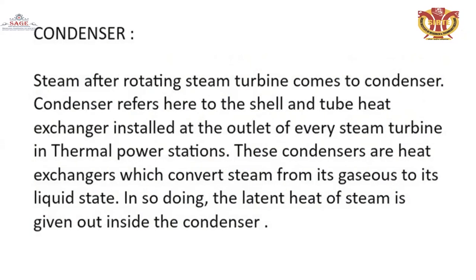The condenser is an important part of the steam power plant. Steam after rotating the steam turbine comes to the condenser. The steam is condensed by the cooling water supplied from the cooling tower. A shell-and-tube type heat exchanger is generally used and installed at the outlet of every steam turbine in the thermal power plant. These condensers convert steam from the gaseous to the liquid state, and the latent heat of steam is given out inside the condenser.